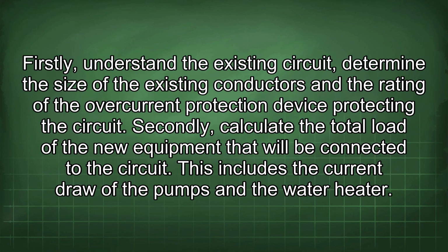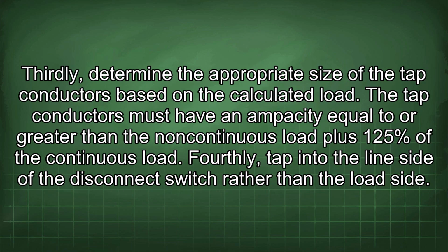Firstly, understand the existing circuit, determine the size of the existing conductors and the rating of the overcurrent protection device protecting the circuit. Secondly, calculate the total load of the new equipment that will be connected to the circuit. This includes the current draw of the pumps and the water heater. Thirdly, determine the appropriate size of the tap conductors based on the calculated load.